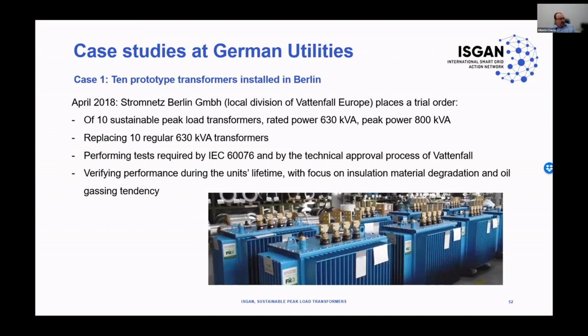So the question that usually comes from the utility and the end user to the OEM is, how mature is this technology, and does any transformer exist that fits the SPL concept that we just saw? The best answer that we can provide as OEM is to show a couple of samples of projects that we have done with some utilities in Europe. And we will start with one case that we did with Vattenfall, with Stromnetz Berlin, where we delivered to this utility 10 SPL type transformers, 630 kVA as nominal power, 800 kVA as SPL power.